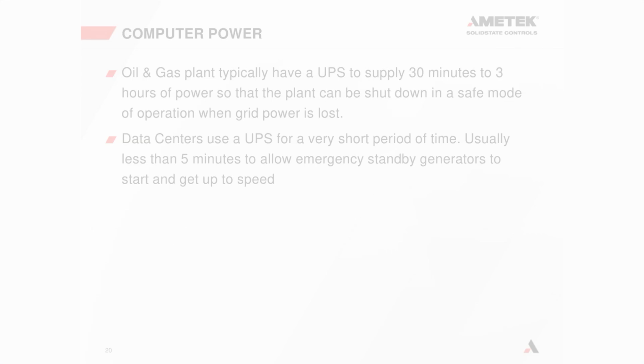In a data center, the UPS is for a much shorter period of time. It's usually around 5 minutes that the battery is sized for, because for a data center we're talking megawatts of power, a huge amount of power. To have a battery back up that much power for a considerable amount of time, the battery would need to be huge and extremely expensive.